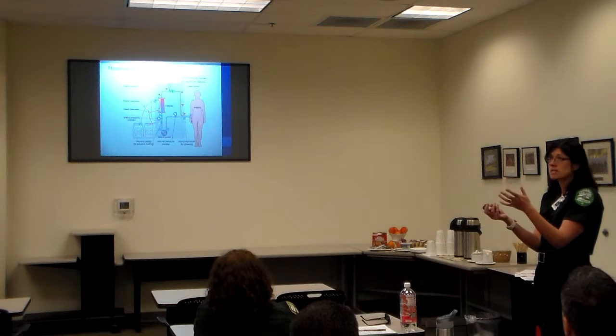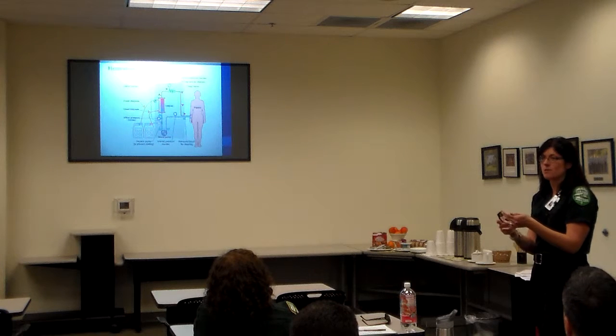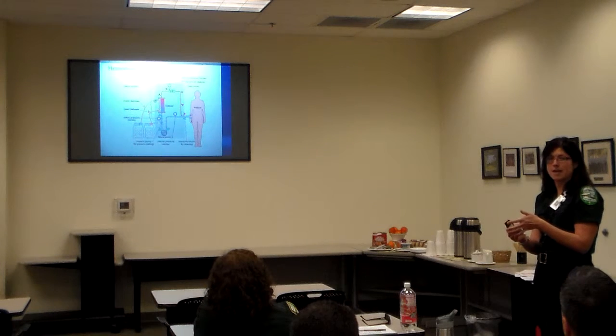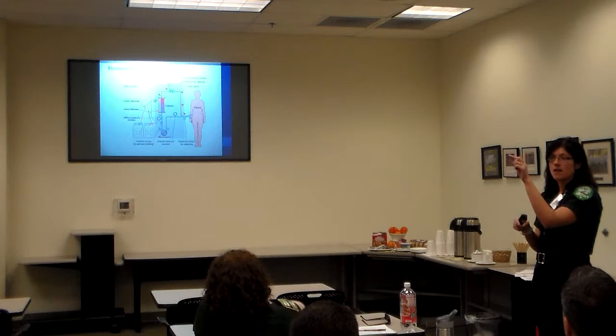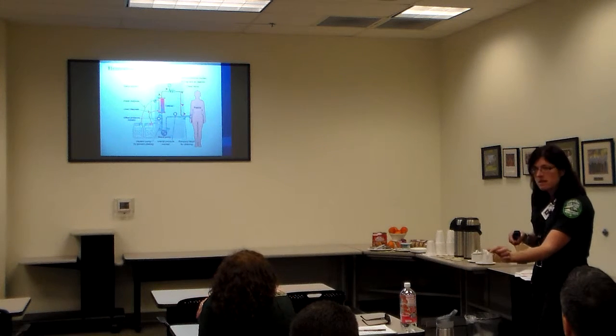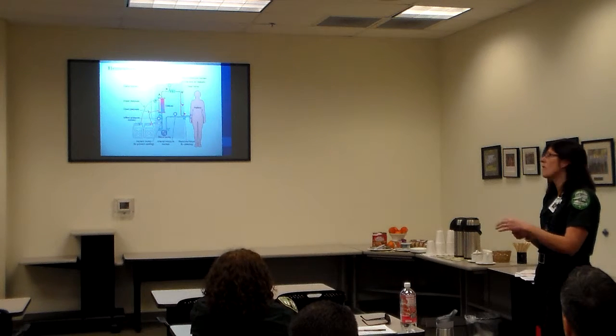it's all dialed in. In the old days, we used to have to calculate it. We'd have to say what dialyzer we're using, so we know what the coefficients are of that dialyzer. We'd go on a little table and say, okay, the patient's got 3 kilos to lose. I need to have a little dial, and I need to dial in what we call the TMP, transmembrane pressure, to figure out what fluids come up.